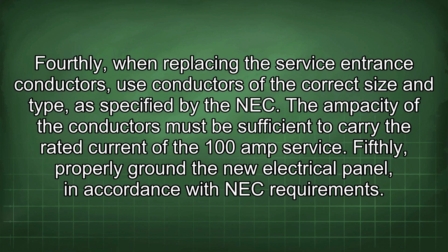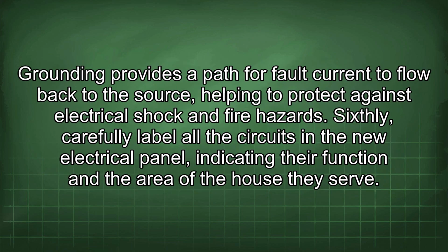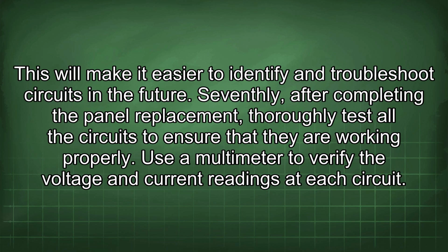Fifthly, properly ground the new electrical panel in accordance with NEC requirements. Grounding provides a path for fault current to flow back to the source, helping to protect against electrical shock and fire hazards. Sixthly, carefully label all the circuits in the new electrical panel, indicating their function and the area of the house they serve. This will make it easier to identify and troubleshoot circuits in the future. Seventhly, after completing the panel replacement, thoroughly test all the circuits to ensure that they are working properly. Use a multimeter to verify the voltage and current readings at each circuit.